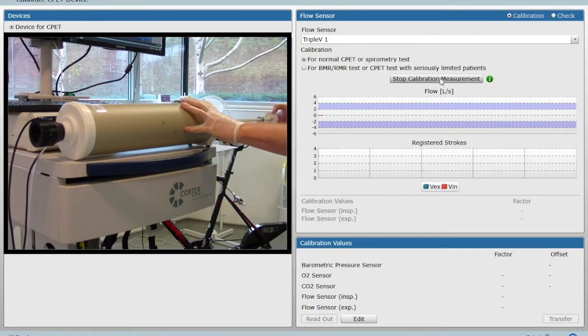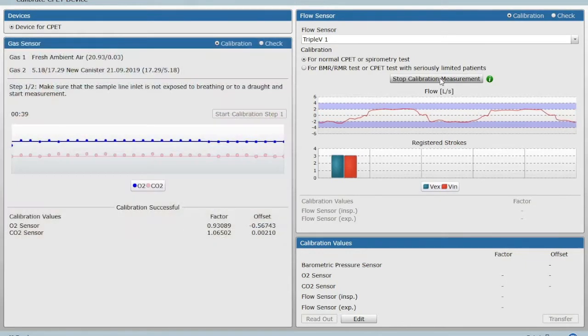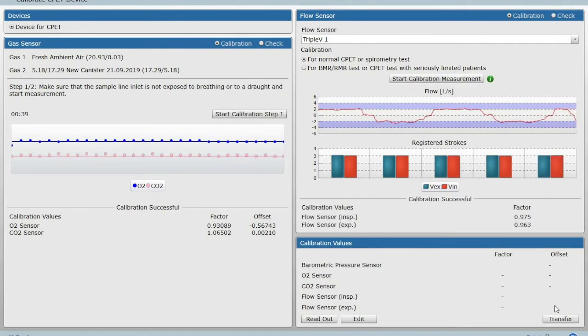The calibration of the flow sensor is done by using a 3-litre syringe. Once attached, the syringe is plunged a minimum of 5 times in order to push the 3 litres through the device. The calibration determines how far this deviates from the 3 litres that's known. We can then confirm the settings of the calibration and proceed on to the next stage of the test preparation.